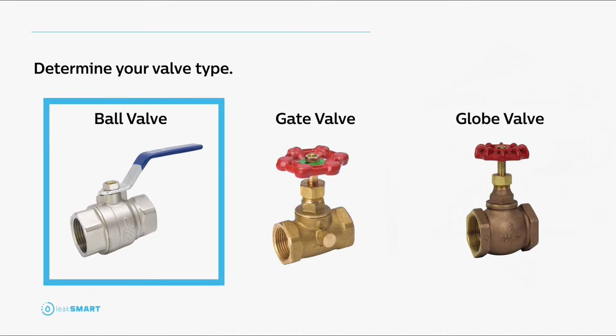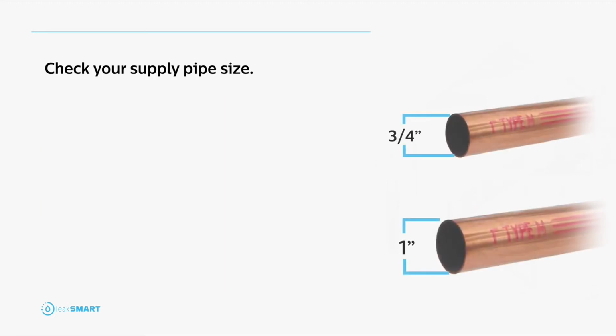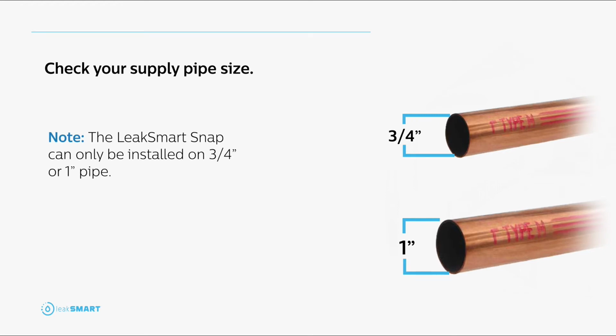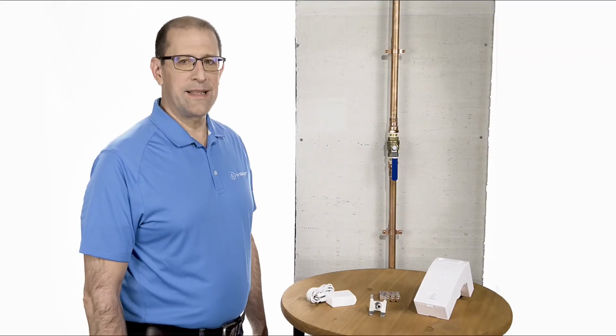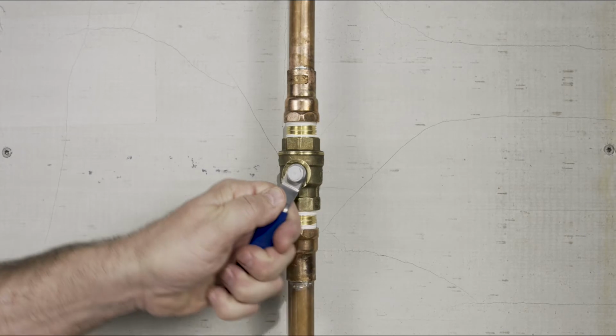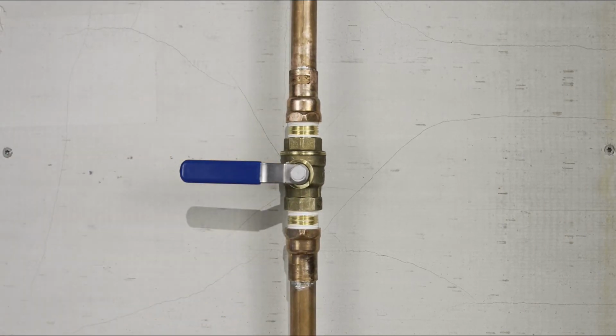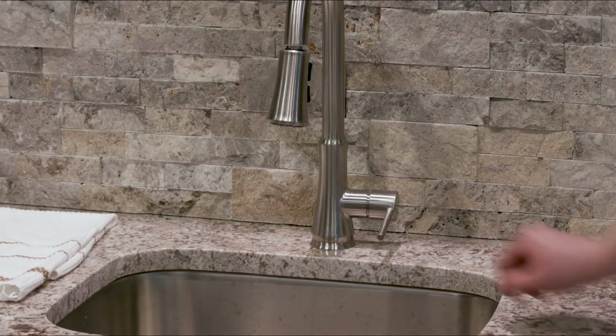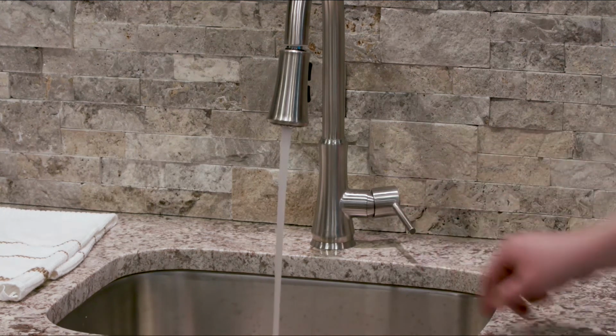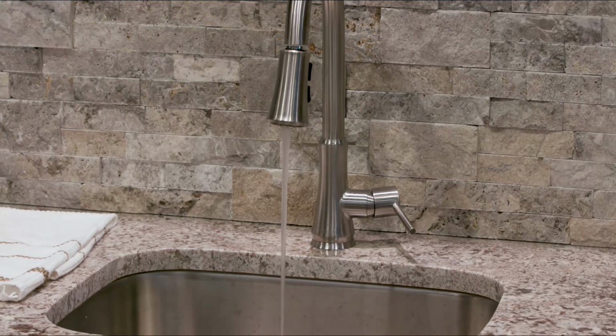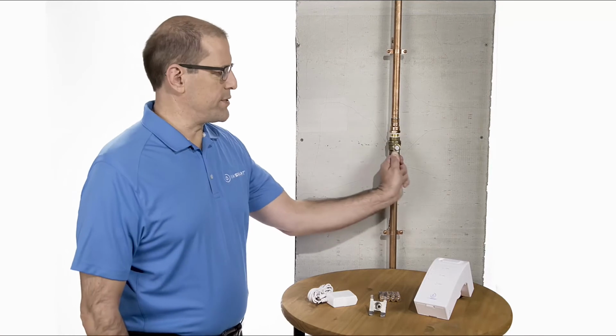To determine if the LeakSMART Snap is compatible with the ball valve, you will first need to check the size of the supply pipe. The LeakSMART Snap can only be installed on a 3/4 or 1-inch pipe. Make sure the ball valve is functional and that you can completely shut it off by hand without tools. Once you've manually turned the valve off, open the nearest faucet to assure that the valve did turn the water off. If it did not, you will need to replace the valve prior to installing the snap. Then, turn the valve to the open position.